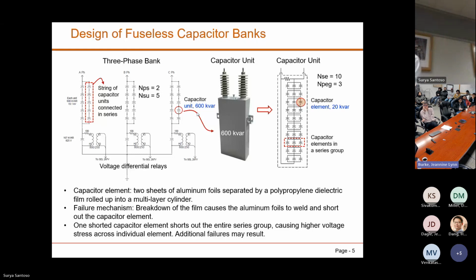Suppose that one fails and takes out the entire series group. As a result, the next group, or any group in here, will experience higher voltage stress. That will cause the dielectric to break down even faster, an accelerated breakdown. So at the end, you may have multiple capacitor units that have shorted elements. Now we need to understand the consequence of shorted elements.